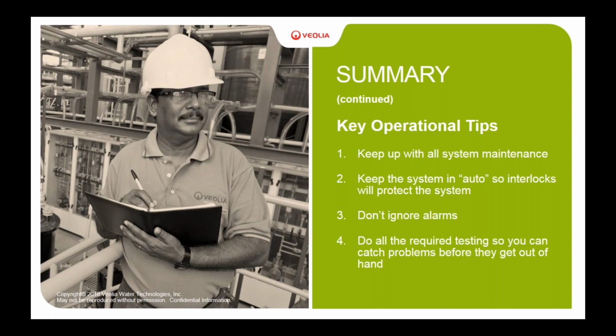Keep the system in auto as much as possible. How many times do things get killed because somebody put something in manual for just a short period of time and forgot to put it back? That's probably one of the number one causes of pH out of control. All of you do it. Everybody does it. You throw something in manual real quick because you need to prime the pump. Something's not pumping, you throw it in manual to see what's working, and you forget to put it back in auto.